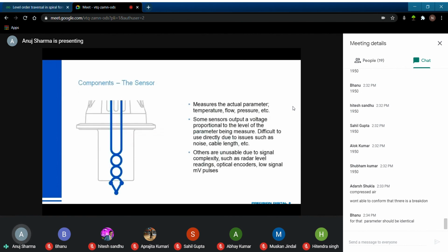The first element is the sensor. This isn't actually part of the 4 to 20 milliamp current loop itself, but obviously it's a critical component. This is what's actually measuring whatever it is you're trying to provide a 4 to 20 milliamp output from. In the case of a flow system, this could be a turbine flow meter that would provide a small millivolt pulse output. It could be a thermocouple or an RTD that's in contact with something reading the temperature. It could be the optical encoder that's reading pulse outputs from something that spins, or it could be the actual ultrasonic emitters on an ultrasonic level transmitter.